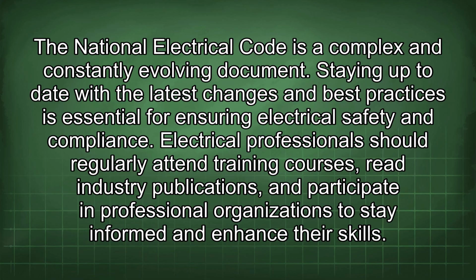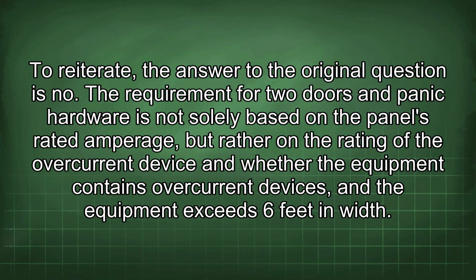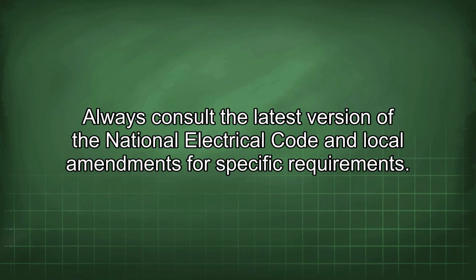To reiterate, the answer to the original question is no. The requirement for 2 doors and panic hardware is not solely based on the panel's rated amperage, but rather on the rating of the overcurrent device and whether the equipment contains overcurrent devices, and the equipment exceeds 6 feet in width. Always consult the latest version of the National Electrical Code and local amendments for specific requirements.